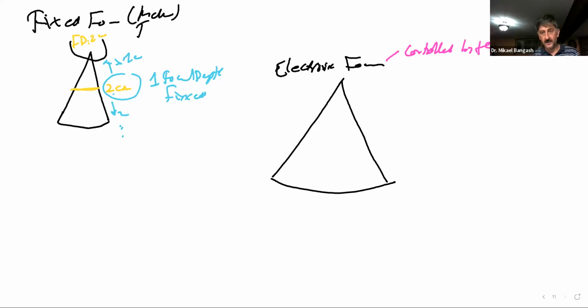The actual details of that we'll talk more about in chapter number 12. But here it's not the configuration or the construction or the makeup of the transducer alone that will determine the focal point, but that along with the way that the electronics of our ultrasound system works.